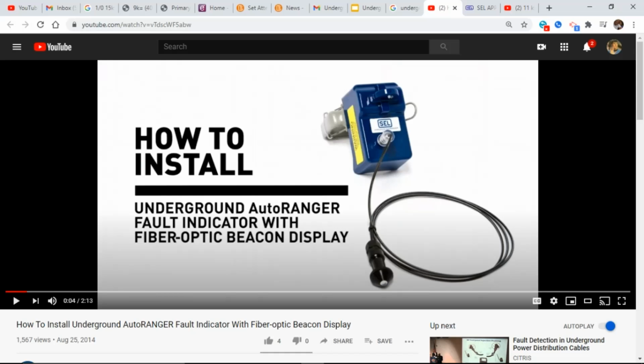Now, the drawback of this one is it's battery powered. Every time you have a fault on the conductor, you have to have a battery in here to flash the light that comes down here, and they do have a lifetime. The ones we were using had a 10-year lifetime. Of course, that can be extended a little bit if you don't have any faults on your cable. The light's never going to flash. But if you have faults on your cable, it's going to shorten that 10-year period also, and you have to go back and change out indicators. So that's a little bit of a drawback to it.